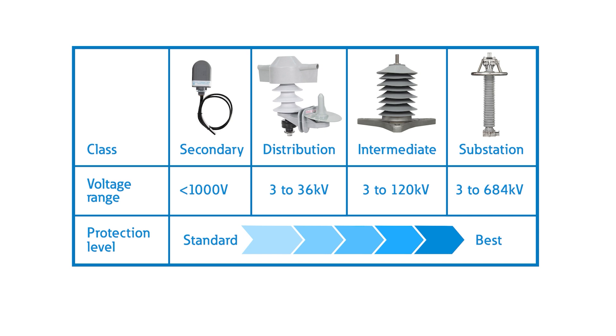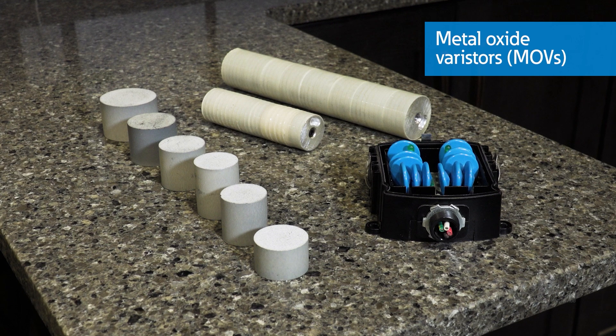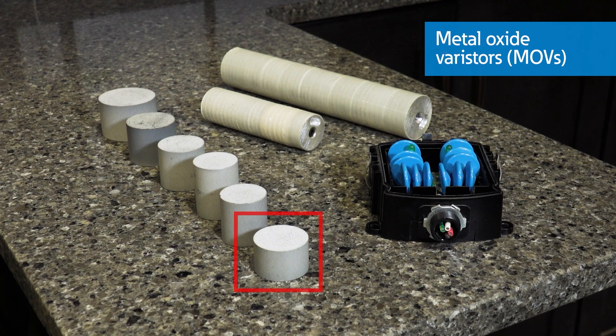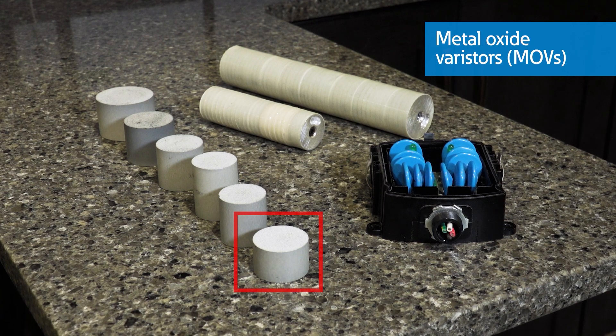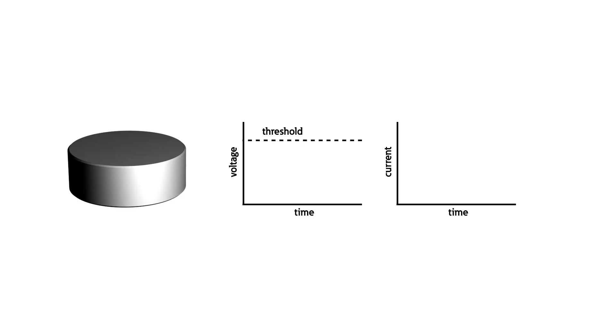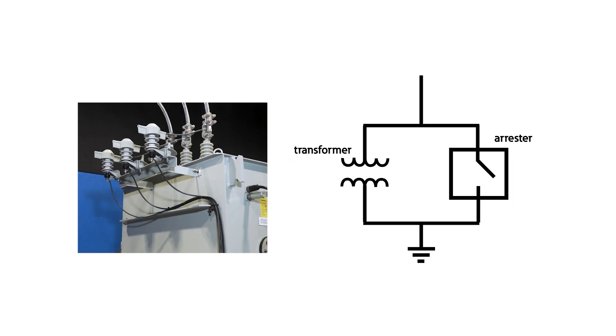All arrestors are mainly comprised of cylindrical blocks called MOVs, or metal oxide varistors. MOVs are materials with non-linear conductive properties. Normally they're insulators, but if the voltage across the block terminals reaches a designated threshold, then the MOVs will suddenly begin to conduct. Utilities will install arrestors as close as possible and in parallel to the piece of equipment that they're trying to protect.